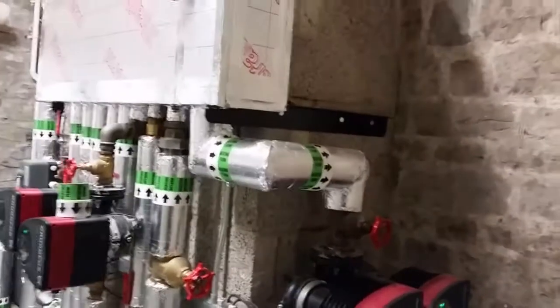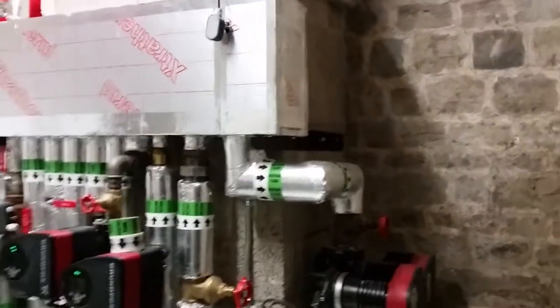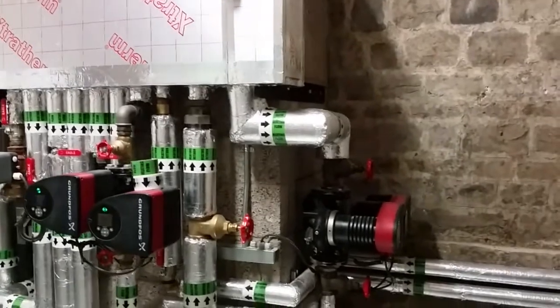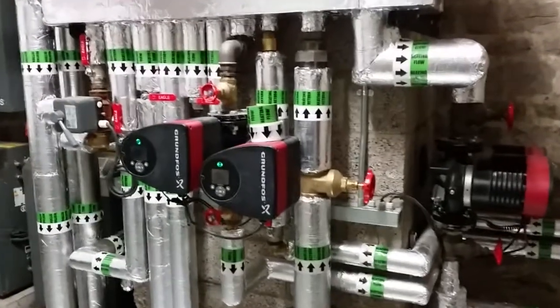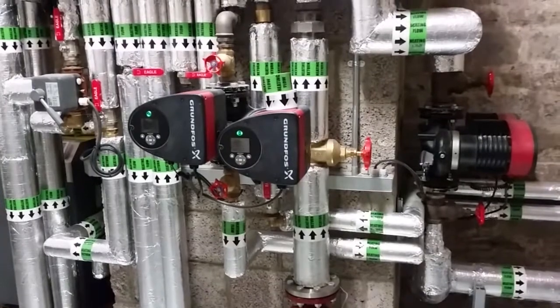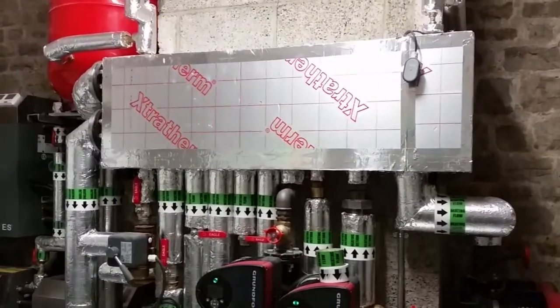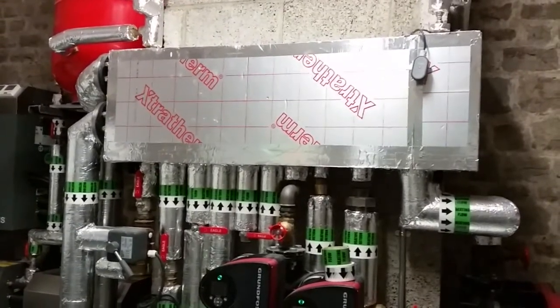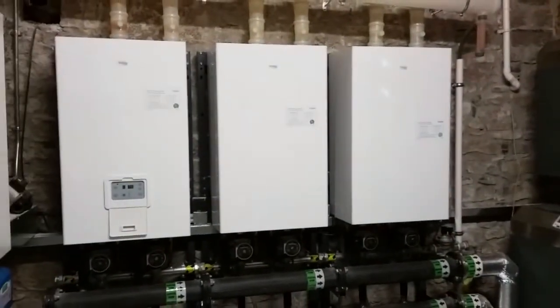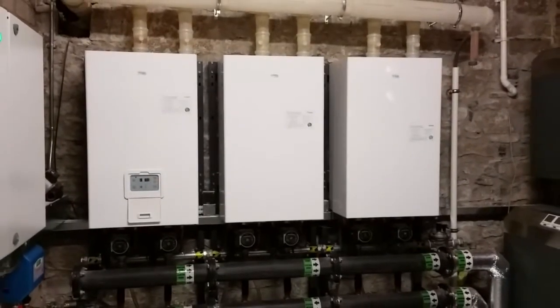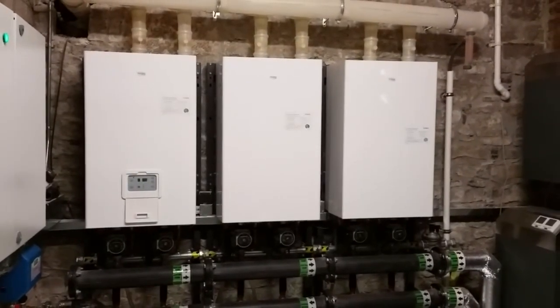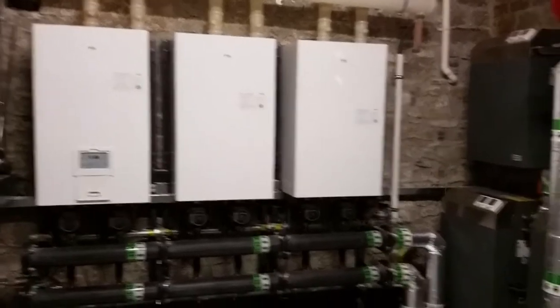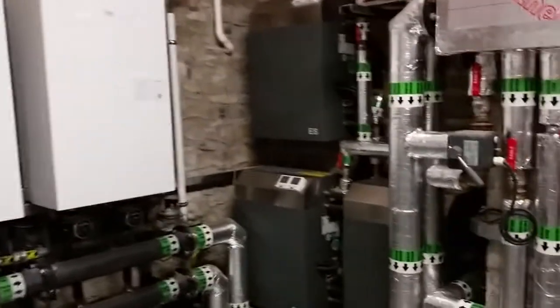The manifold uses the original pipework as a zone, but there is also a second energy zone going to a separate part of the building, again controlled by Grundfos speed control pumps from the energy zone manifold. This patented device allows for high temperature and low temperature appliances to be interconnected, as in this situation where there are three wall-hung condensing modulating boilers with built-in weather compensation, and also three 20 kilowatt heat pumps.